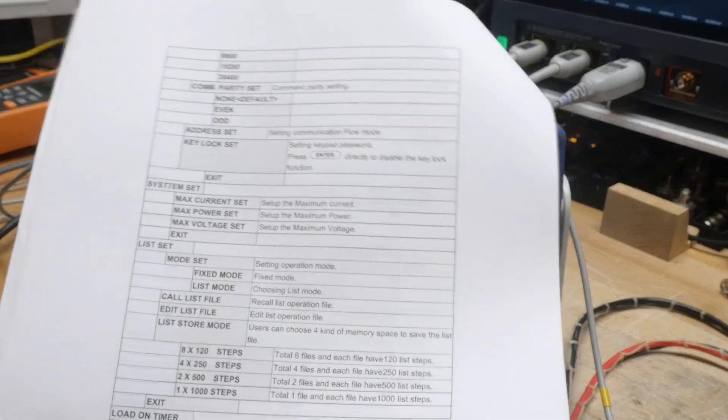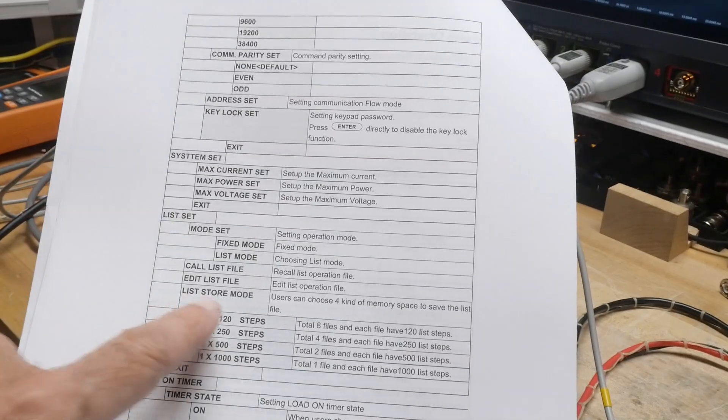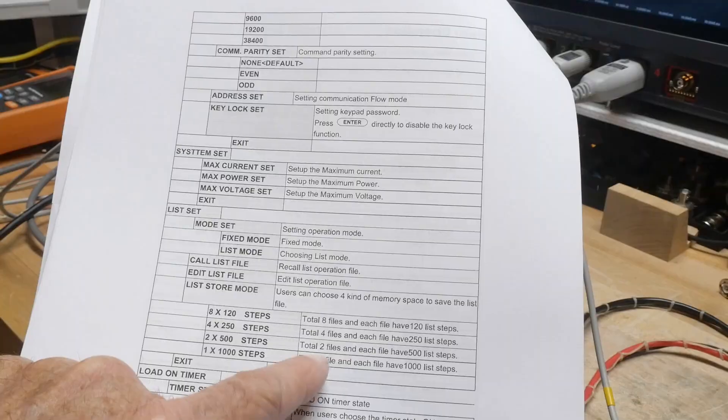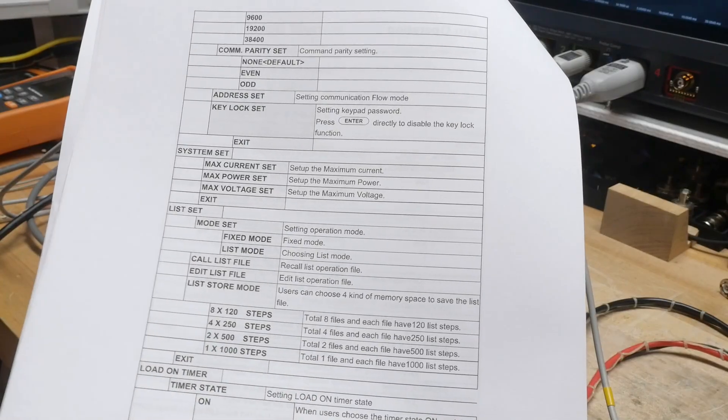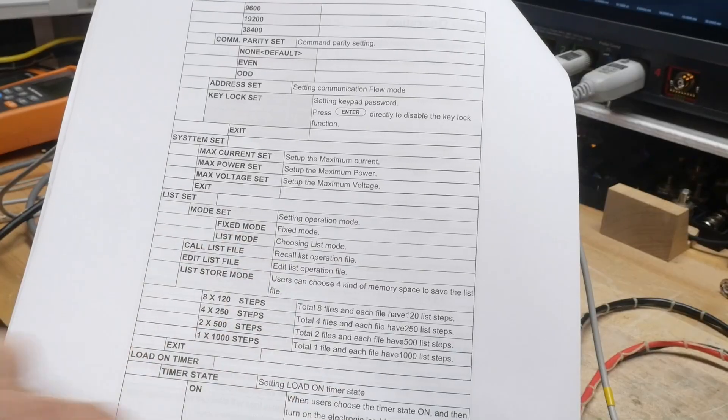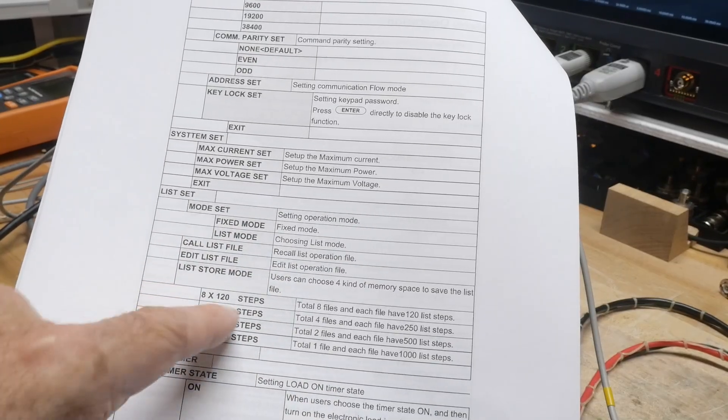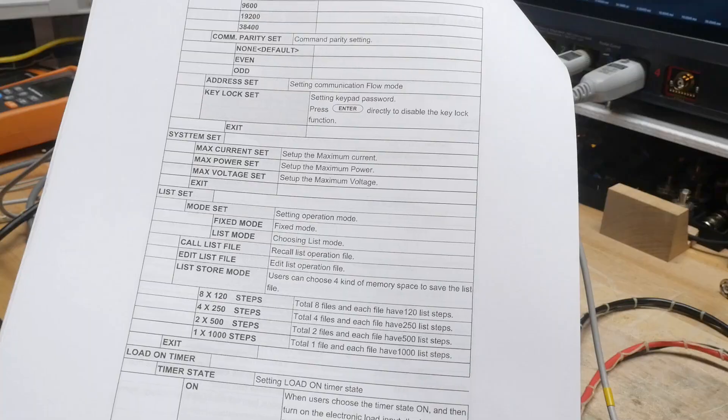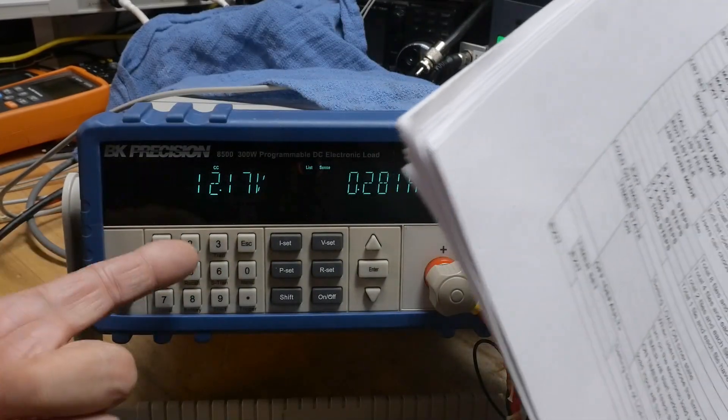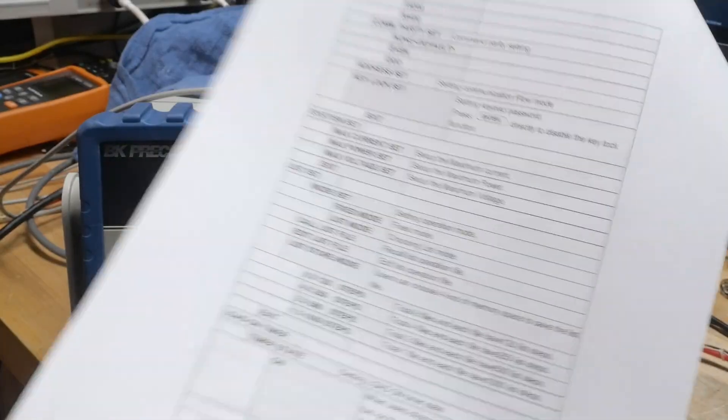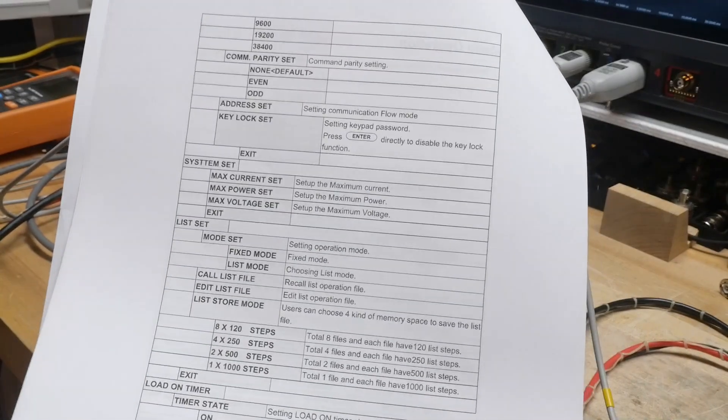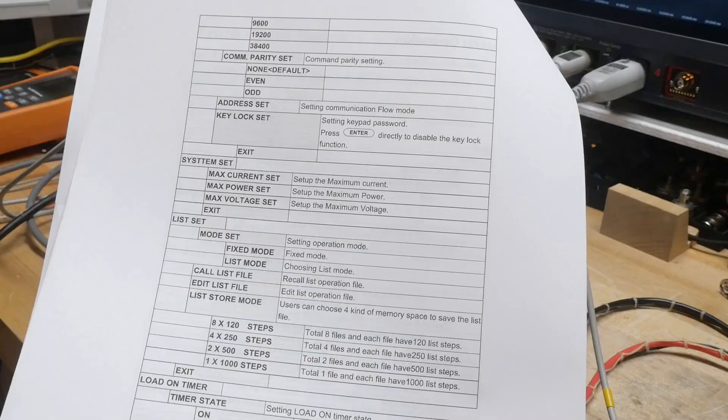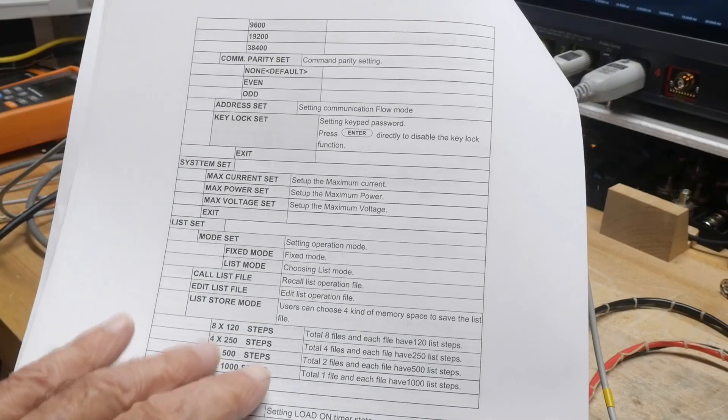Now, the list function is very interesting. So the list function, you can have one file that has a thousand different levels, or you can have two files that have 500 levels, or eight files that have 120 different levels. And that's the memory limitation of the machine, the EEPROM - it remembers all of this.